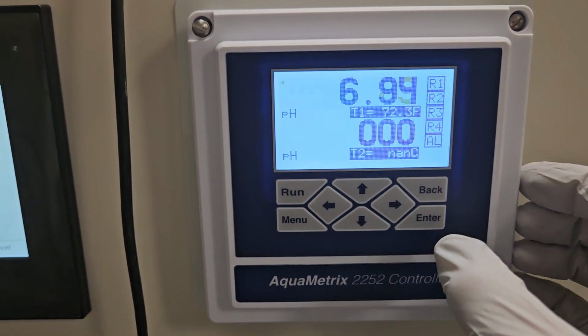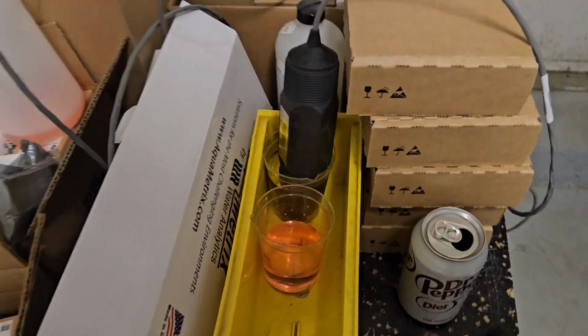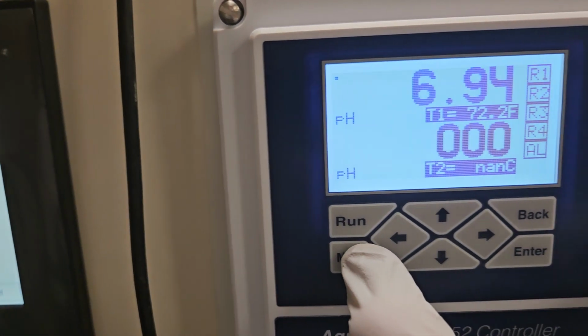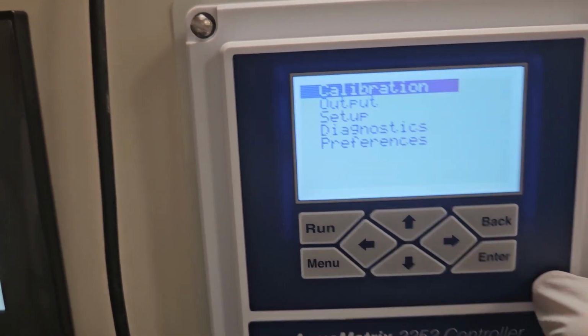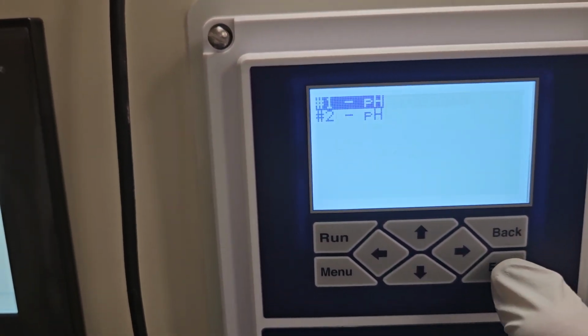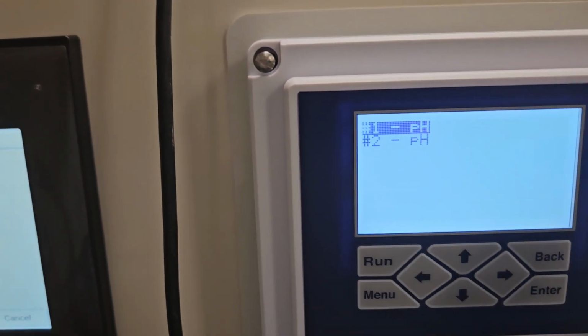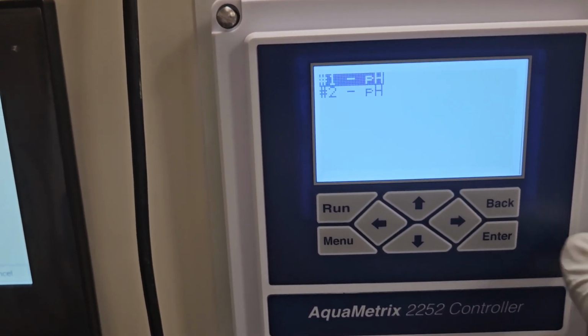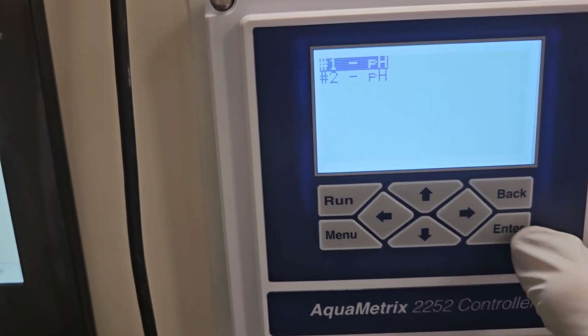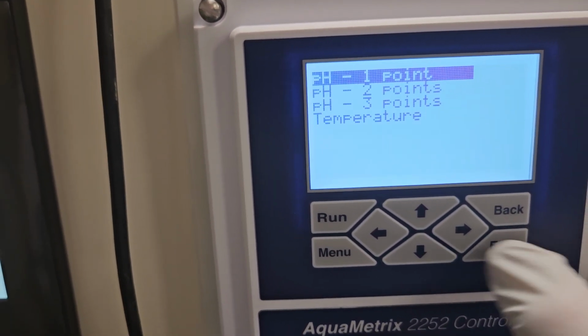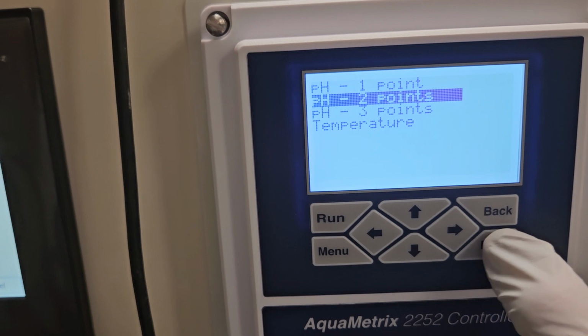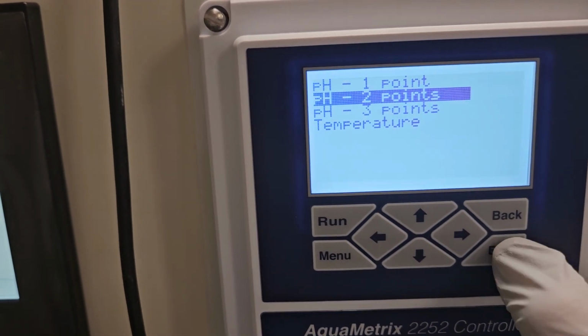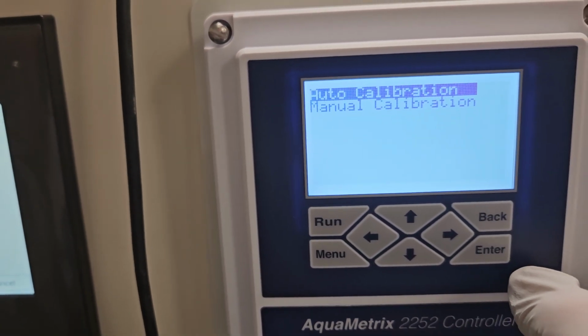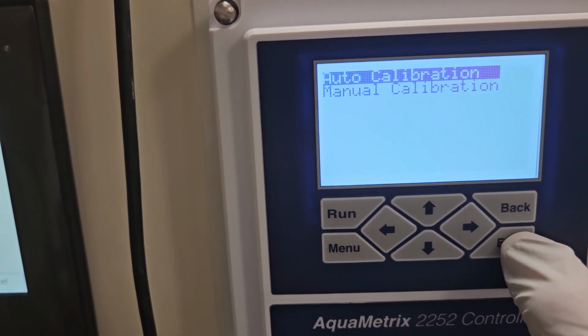Okay, we're going to try to run a calibration now with the pH probe in the yellow buffer solution. Go to menu and enter on calibration. There are two inputs on this meter. Input 1 is the pH probe. Enter there. We're going to go with a 2-point calibration because it's going to use 4 and 7. Enter here. And I'm going to try an auto calibration.